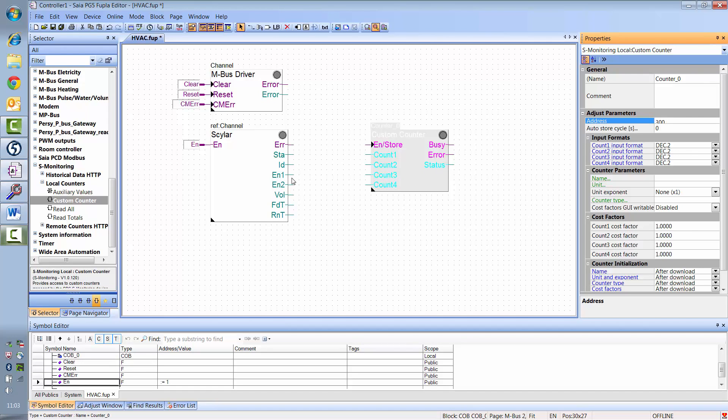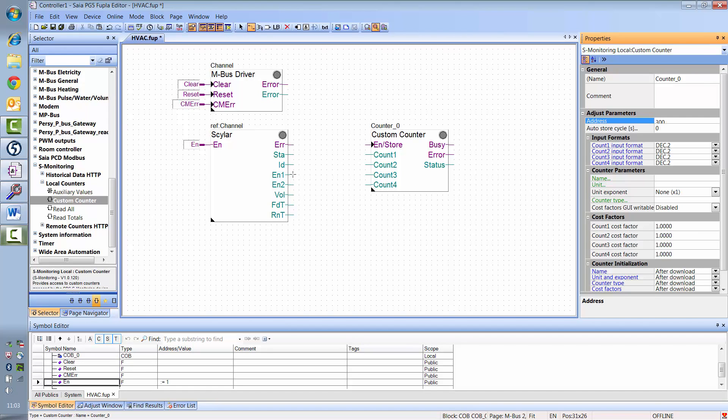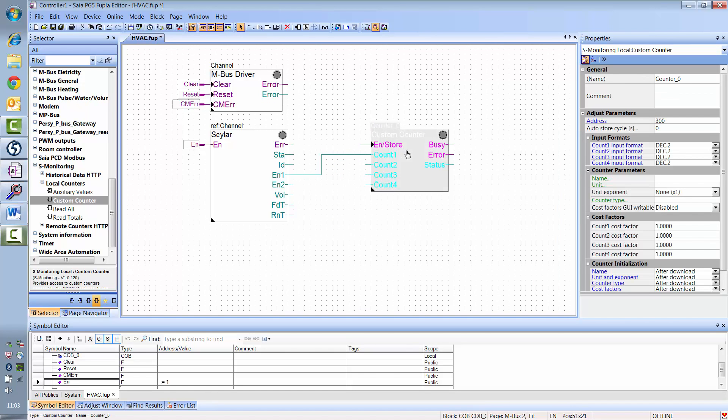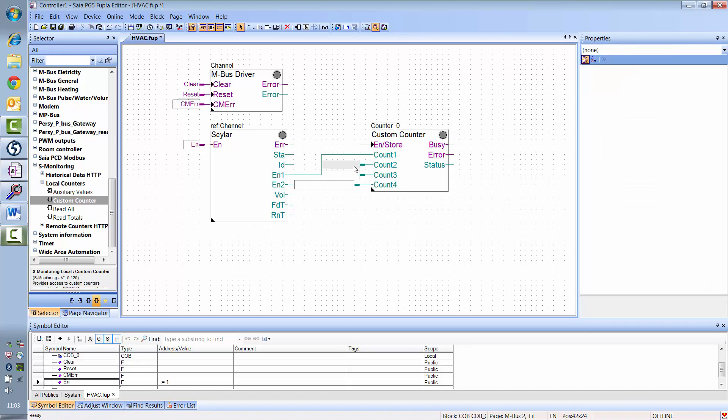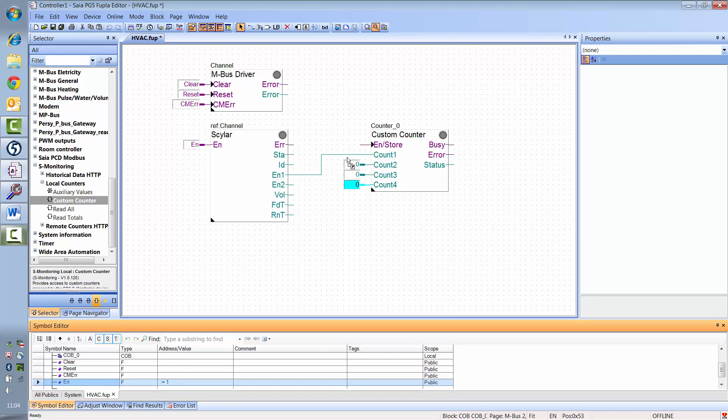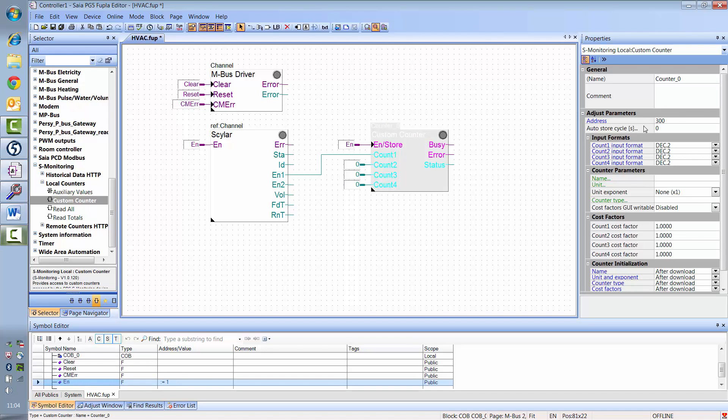I'd now like to link my M-Bus meter's energy value to the custom counter's count value. In this case, the other three possible count values are not needed. In the counter, in addition to the address, I must also set the values input format. In my case, two decimal places is already correct.